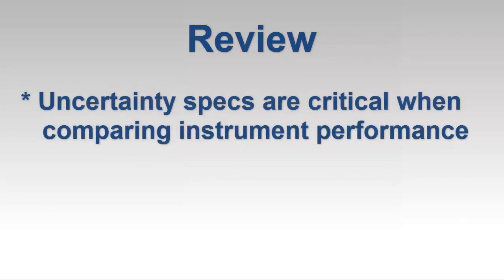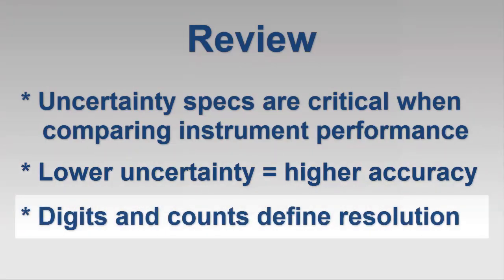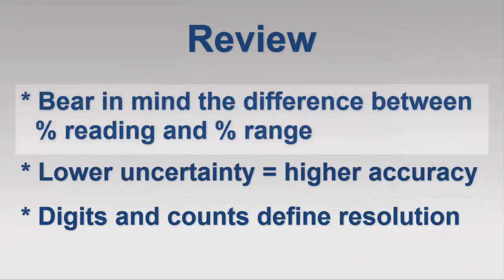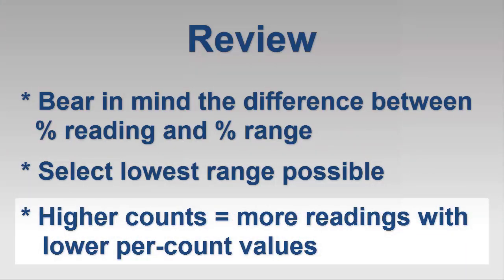Let's review a few key points we've covered. It's important to understand uncertainty specification to properly determine an instrument's accuracy. The lower the uncertainty, the higher the accuracy. Digits and counts define an instrument's resolution, but not its accuracy. When comparing performance, bear in mind whether the instrument's uncertainty is based on percentage of reading or percentage of range. Be sure to select the optimal range, generally the lowest possible, when making a measurement. And finally, high-count instruments can produce more readings with lower uncertainties than low-count instruments.